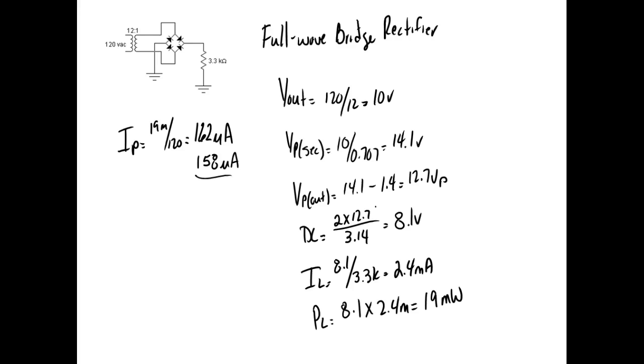But what you got to understand is 158 and 162, the difference is only 4 microamps. And in reality, if you check it, it's not going to measure this anyway, because what we're doing is using 120 volts on the primary. What are the odds of having exactly 120 volts on a primary?